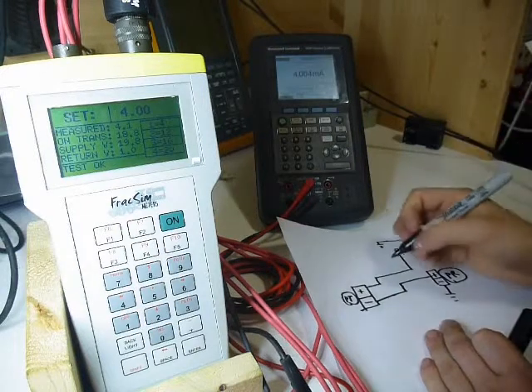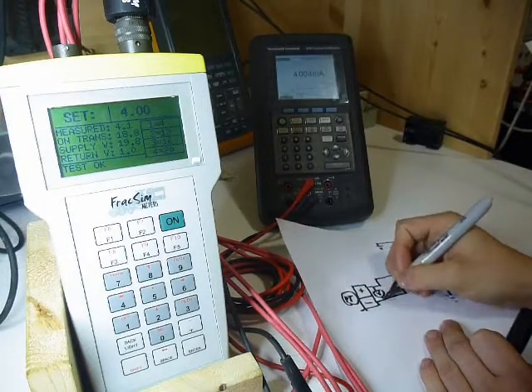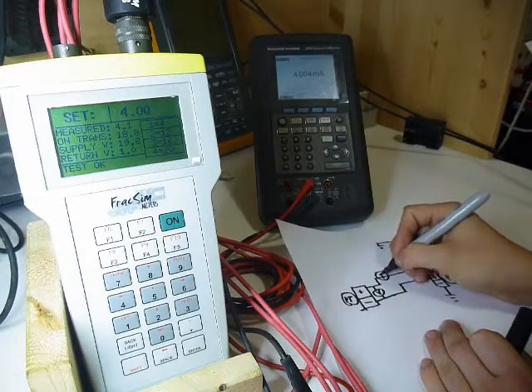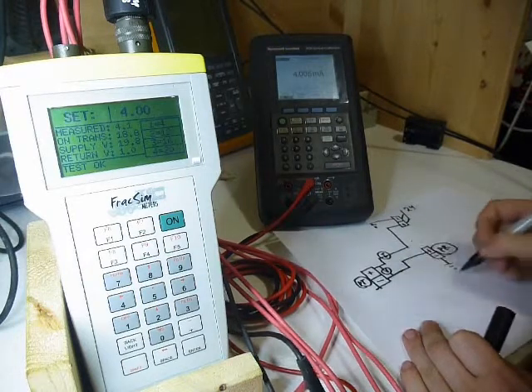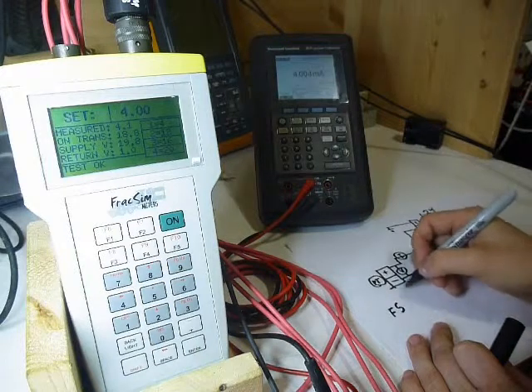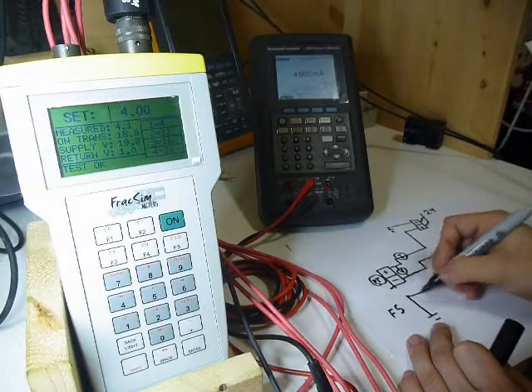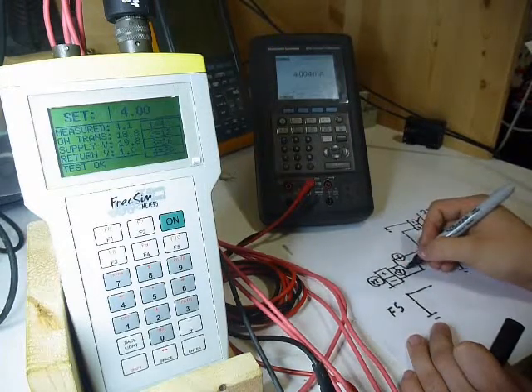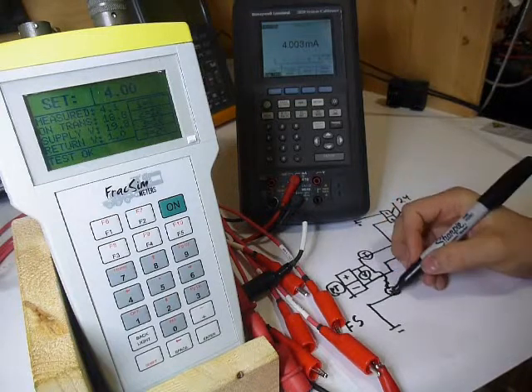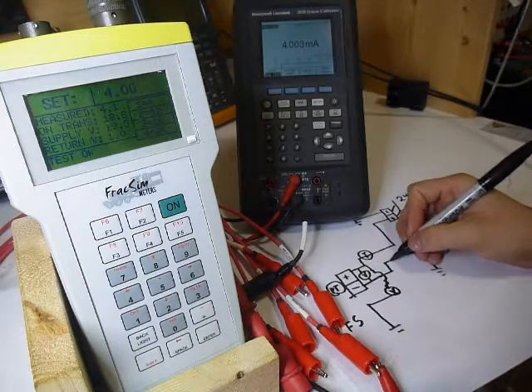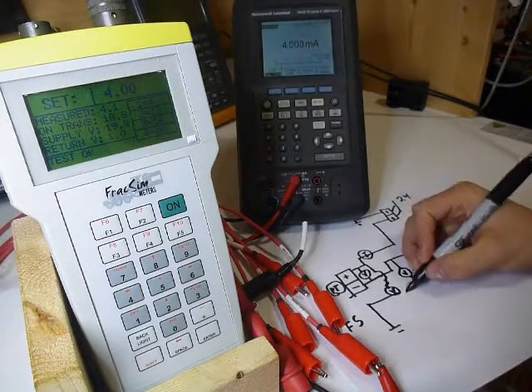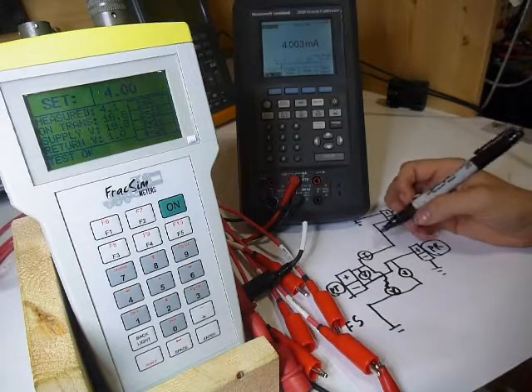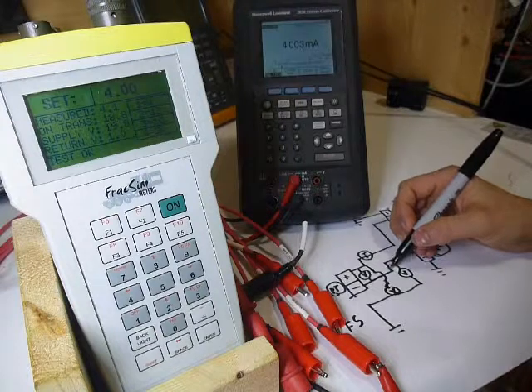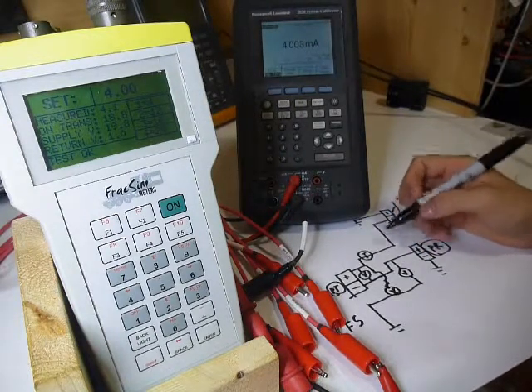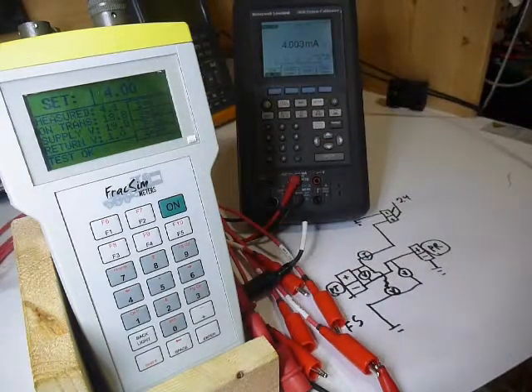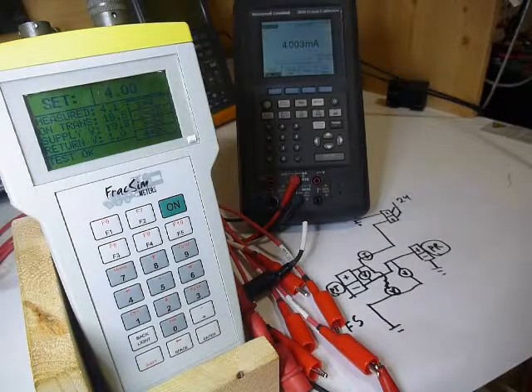Now, normally with 2-wire, the only measurement you could possibly make is the voltage measurement right there, and the current measurement right there. But by adding a third wire, and we'll call this now the Fracsim, by adding that frame ground on the Fracsim, you can actually make this measurement as well from here, from supply to ground, and you can take the voltage measurement from here to ground. And why that's useful, of course, is if you would have possibly a high resistance here or a high resistance here, you could actually see that with the voltage readings here, and then figure out which side of the loop is your issue, either the supply side or the return side.